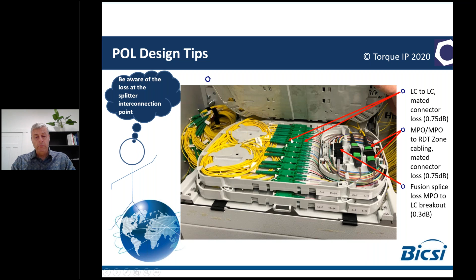We have to remember 0.75 dB loss here for the mated connectors, and 0.3 dB loss for the fusion splice onto the ribbon fiber from the 900 micron cable. So the 900 micron off the LC connectors goes in, and we come out with ribbon cable going into the MPO. We then have another mated pair, MPO to MPO, again 0.75 dB. This fusion splice or the MPO to MPO mated pair and coupling is often missed - since this is a full plug-and-play solution, we have to make sure we pick up all those losses.